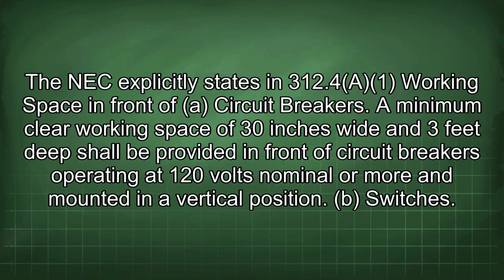The NEC explicitly states in 312.4(a), on working space in front of circuit breakers, that a minimum clear working space of 30 inches wide and 3 feet deep shall be provided in front of circuit breakers operating at 120 volts nominal or more and mounted in a vertical position.